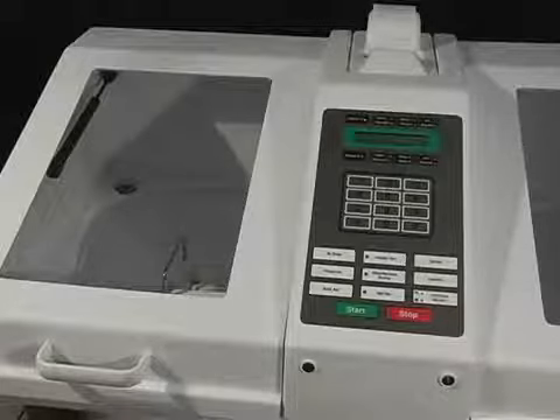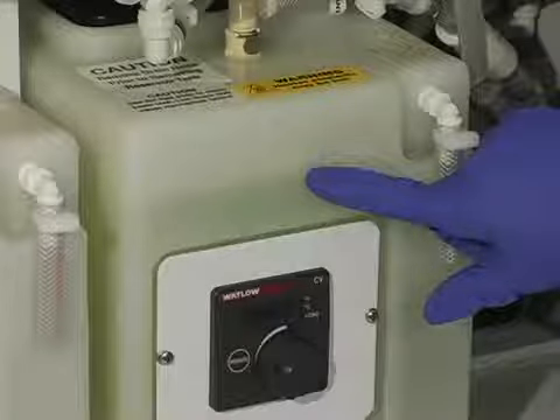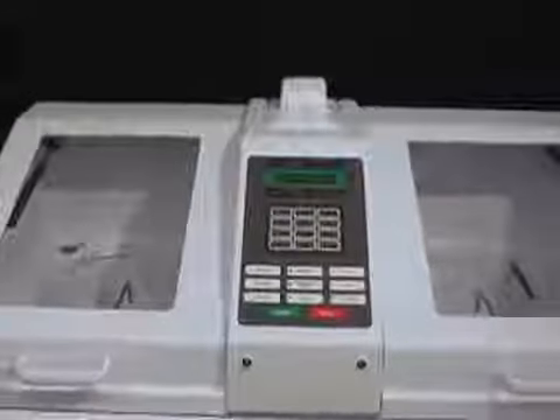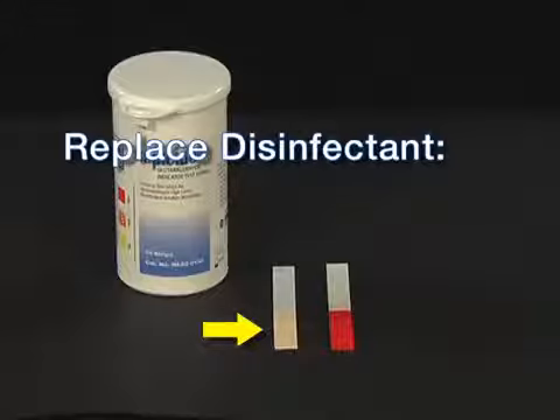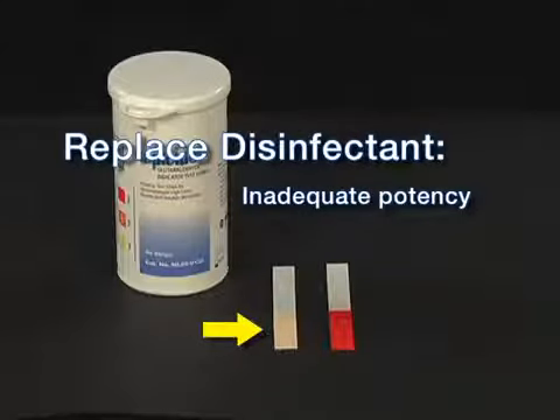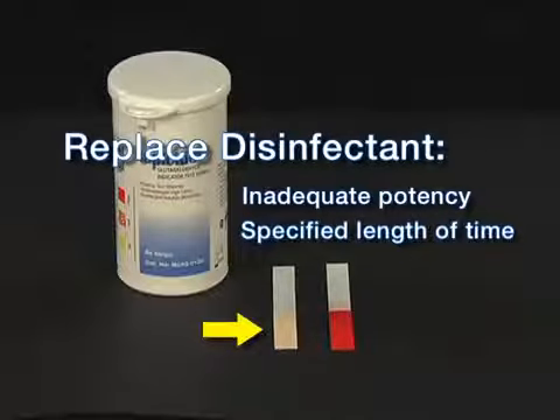When all 4 gallons have been loaded into the reservoir and the DSD-201 is idle, confirm that the disinfectant level has reached the indicator line on the reservoir. Remember that your DSD-201 disinfector contains 2 independent disinfection stations. Each station has its own reservoir and disinfectant filter. The disinfectant on both sides must be changed on schedule.